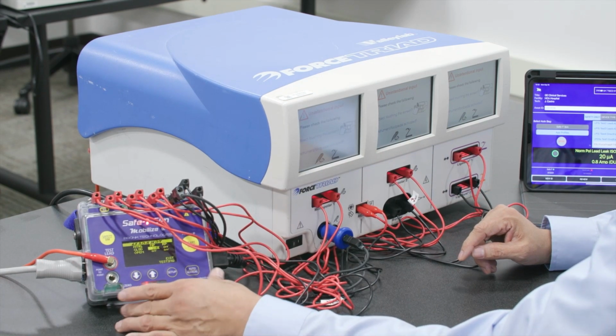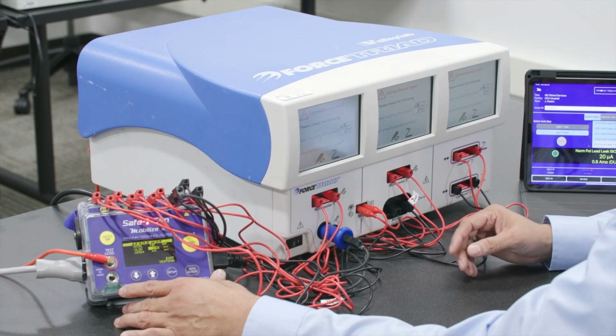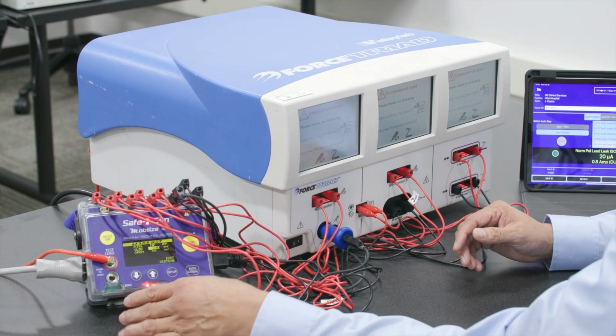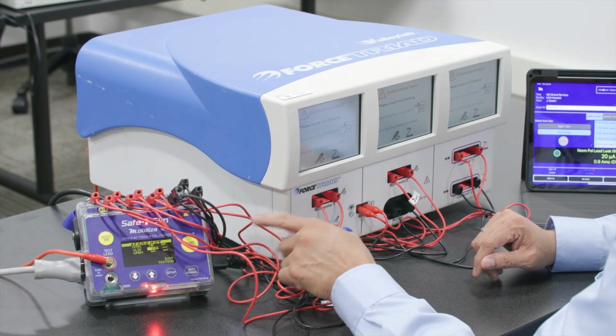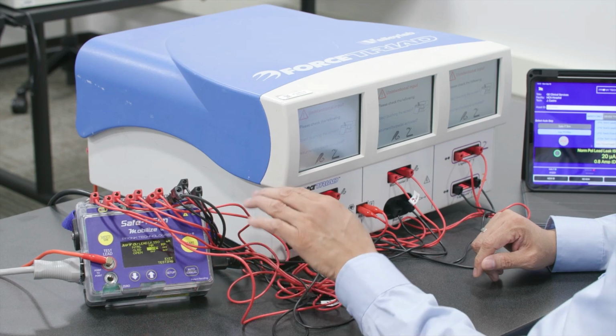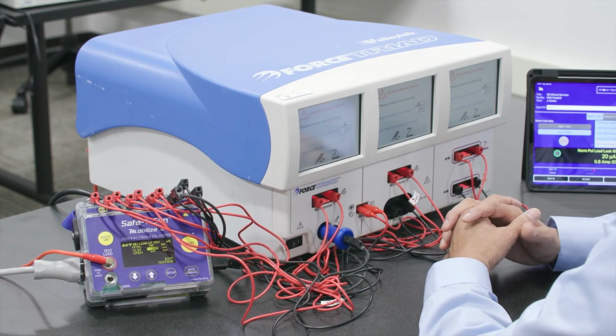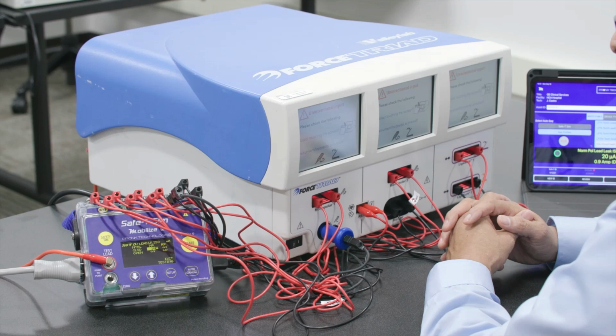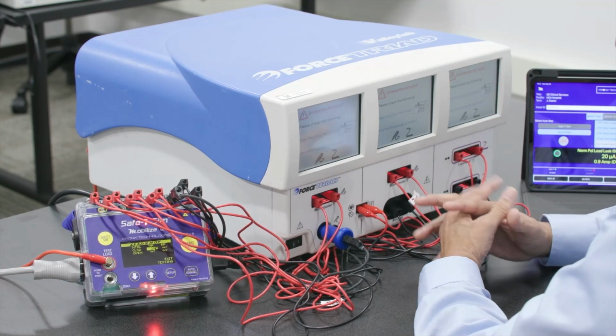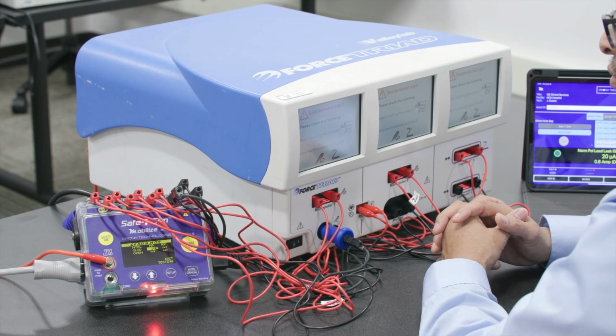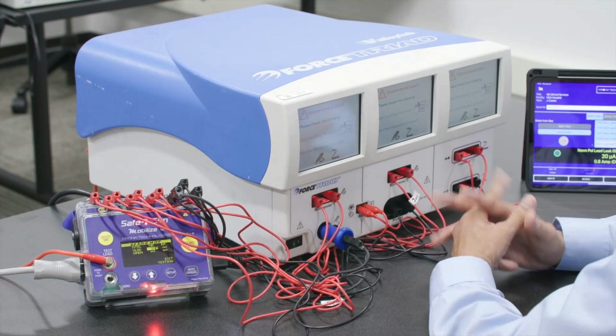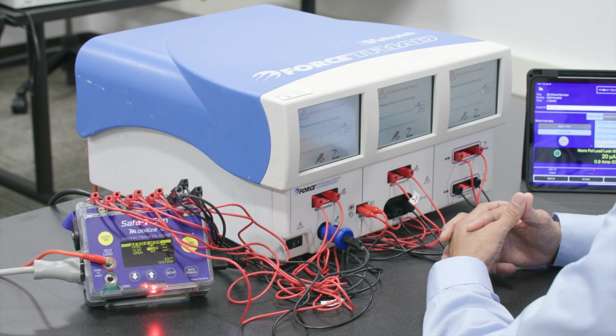So when we get to the leads ISO test, or as I mentioned, the leads MAP test, the main unapplied parts, it's putting 120 volts AC. So this is an indicator of the analyzer letting you know do not touch those leads, because even though they are current limited, you still have mains AC voltage on there at 120 volts AC. It's actually 10% above mains voltage, and so we don't want to touch those leads. So it's going to run that test, and this is just a safety precaution letting you know that those leads are hot.